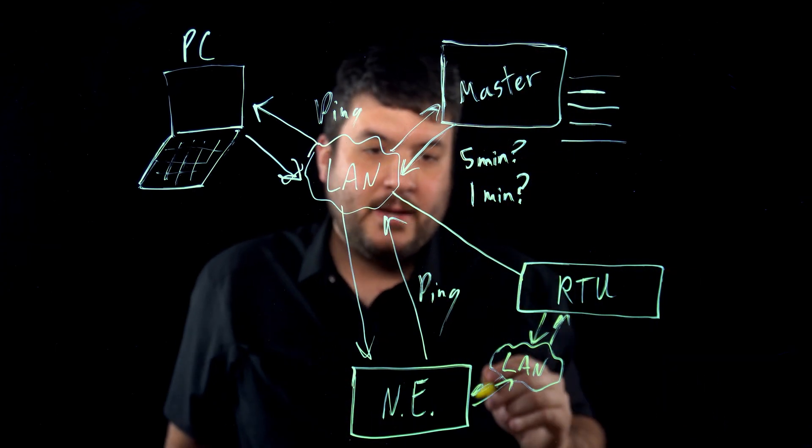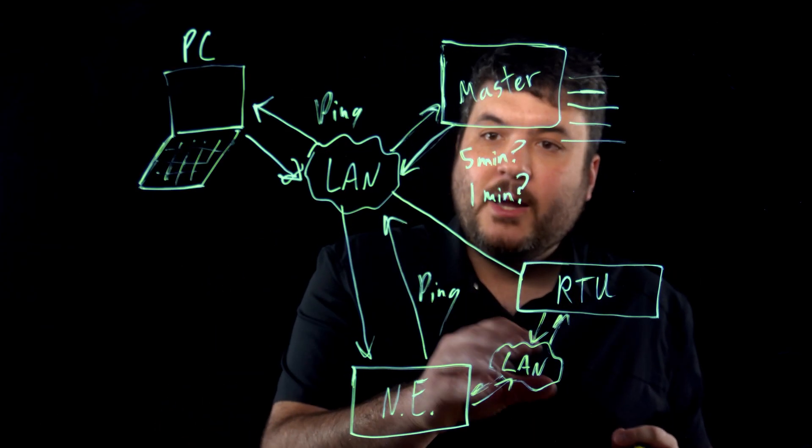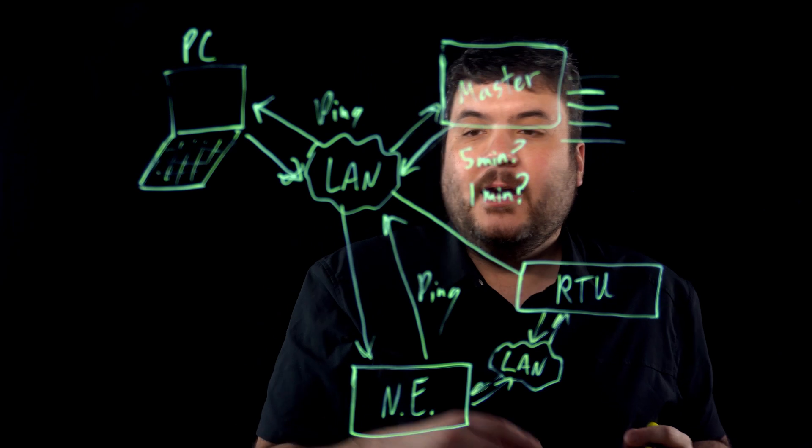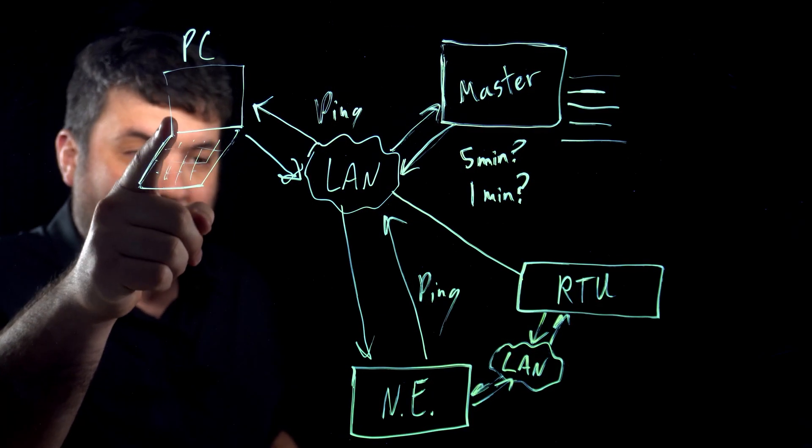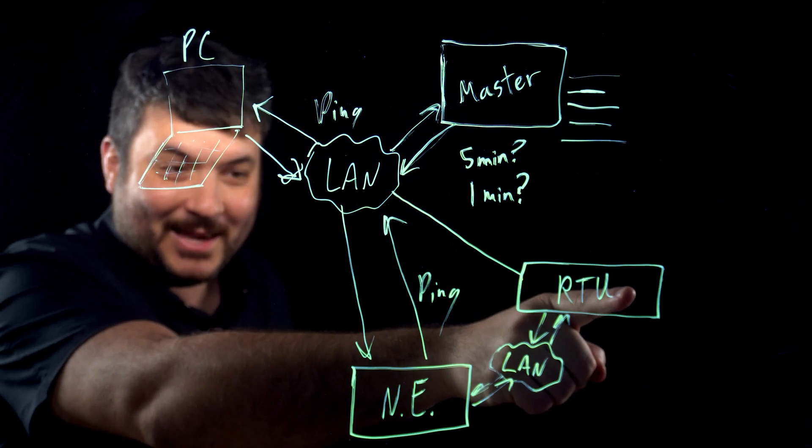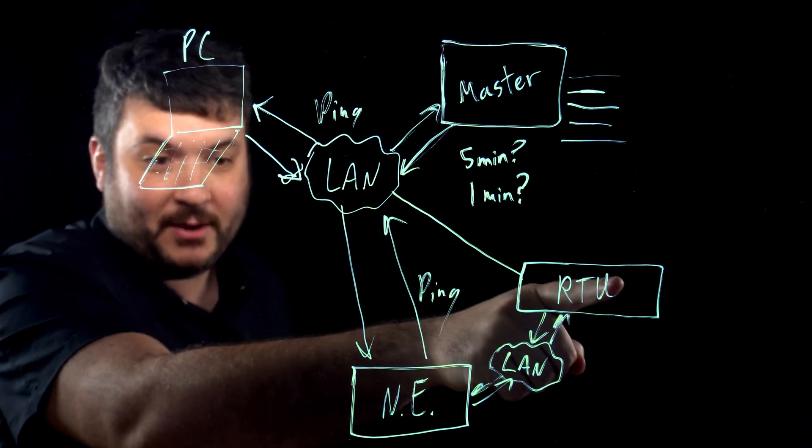So the RTU can handle that independently, and this can just be a different way. It reduces the load on your master. It gives you a different insight. Oftentimes, like on NetGuardian RTUs, we have an ability to use the TTY interface to go from our PC, get into the RTU, and then do a manual ping from that position.